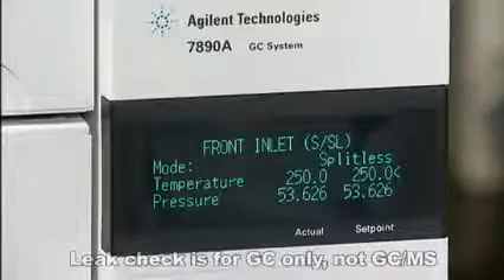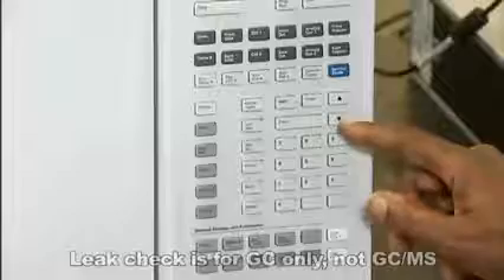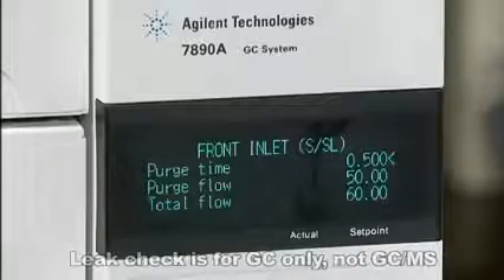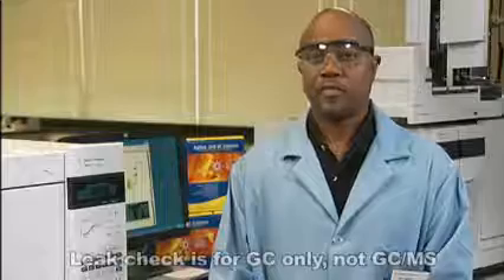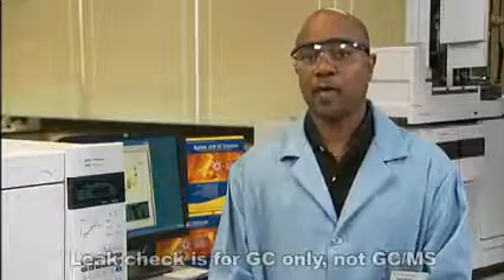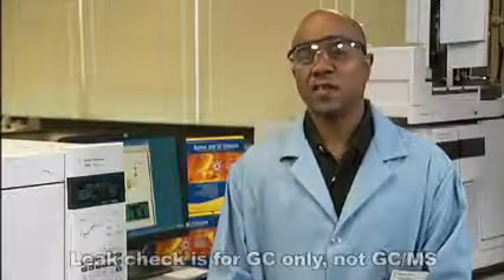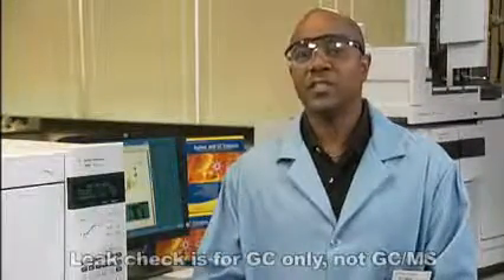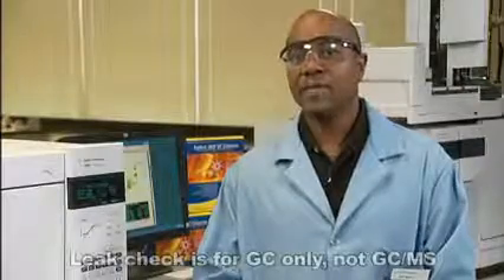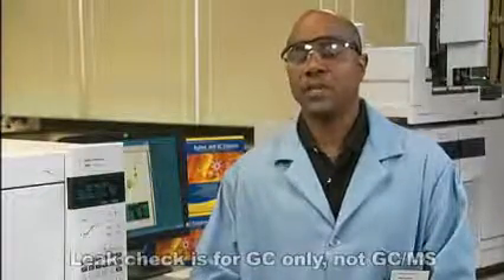You may have to adjust the inlet pressure to achieve your set points of the column flow. Press the prep run to shut off the purge valve. This is the split vent flow. And then change the inlet configuration. You may have to press it twice if your GC is not ready.